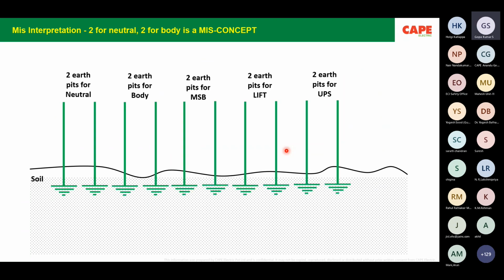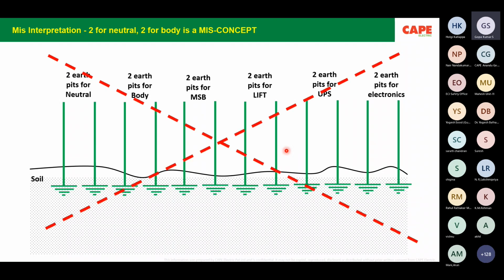When it comes to earthing, the most confusing subject, which I always try to fight: 2 for neutral, 2 for body. Don't get confused by the word earthing. It's just a term for making all metallic parts in your building at a potential equal to the earth potential. So the term earthing or earth has nothing to do with the earth electrode. Two connections for neutral, two connections of body to the earth pit for UPS, for DG, for lift, for electronics: this is absolutely a big mistake. Please don't do it.